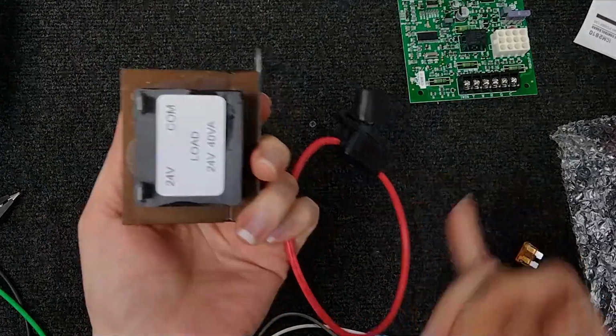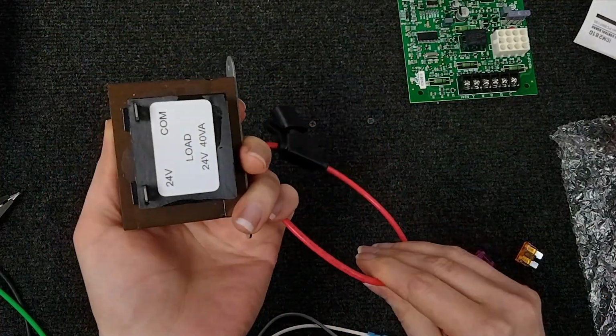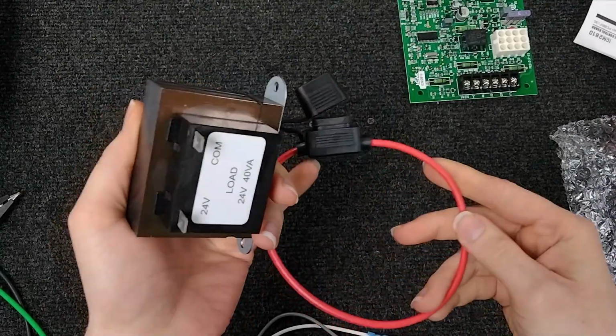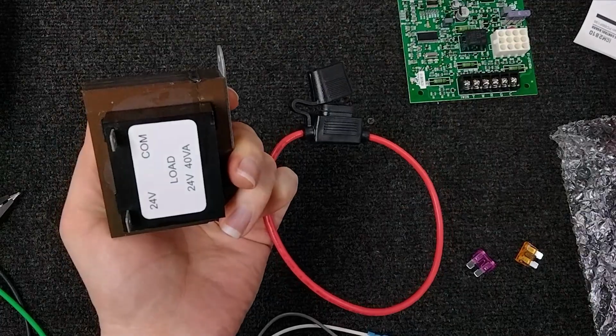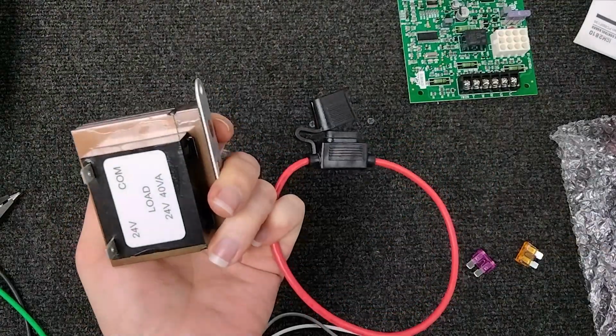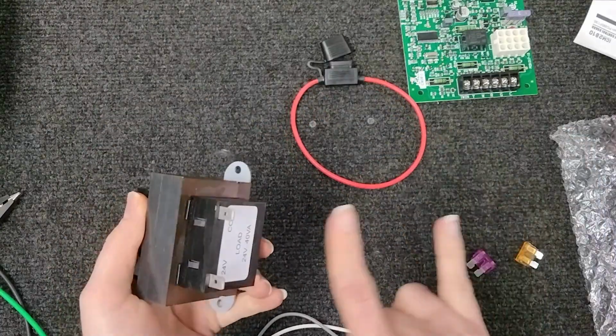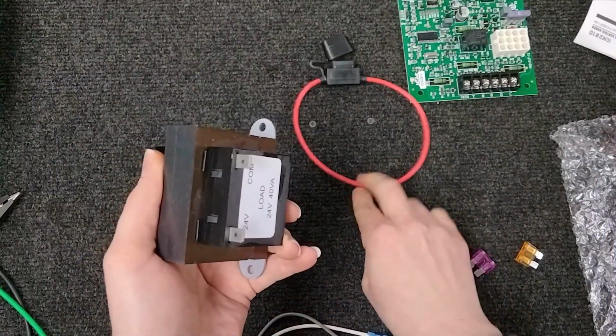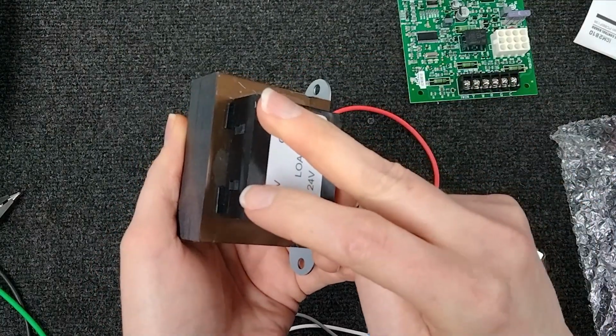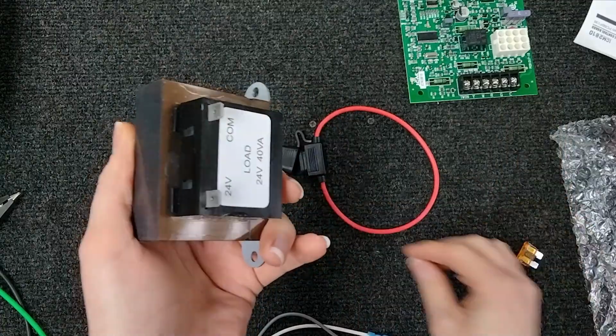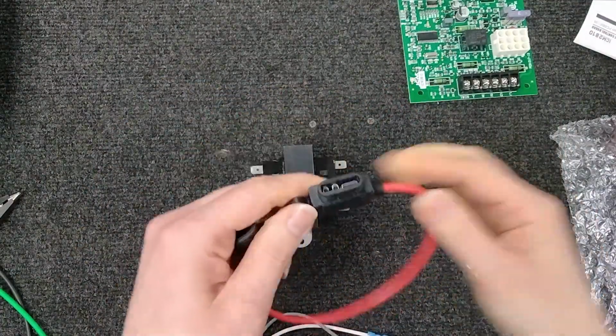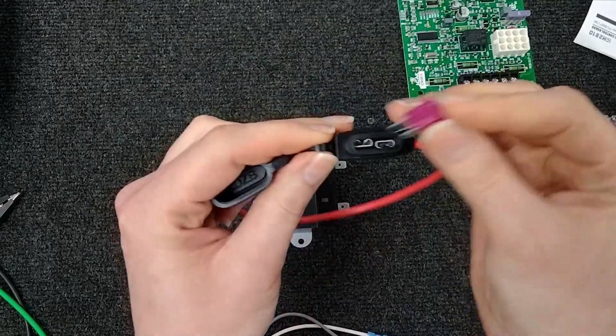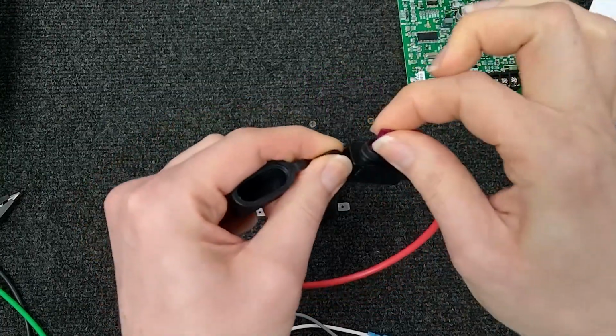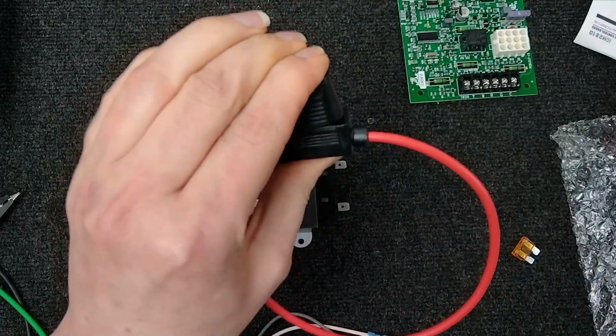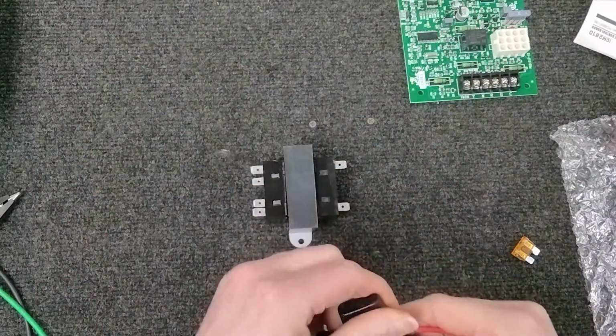Now these would basically be cut, stripped back, and then wire nutted, or however you want to do it. If you want to do the heat shrink, which is really what I prefer to do, it's a lot more safe. Just tie them in to one of these legs. Do not put this one on both. Okay, it only needs to go on one side. And this will prevent a short on your low voltage. And this guy just goes in here like that. Make sure it's all the way in there and snug. And then, boop, it just closes right over there. And that'll catch a low voltage short.